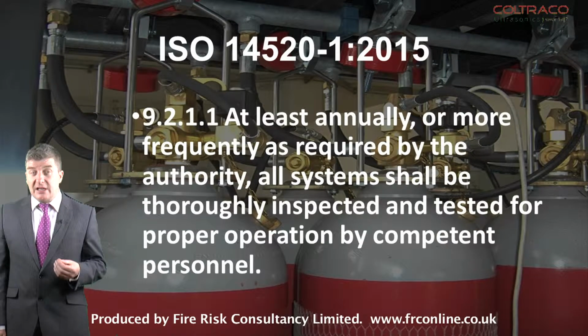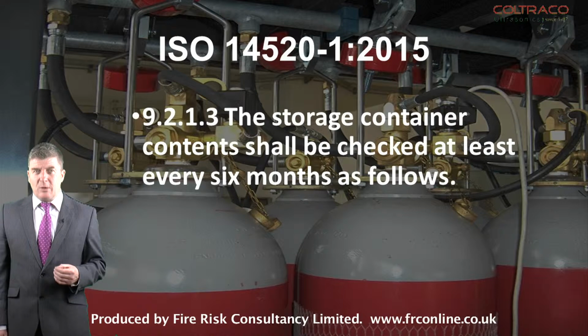another section, at least annually or more frequently as required by the authority, all systems shall be thoroughly inspected and tested for proper operation by competent personnel. 9.2.1.3 says the storage container content shall be checked at least every 6 months as follows.